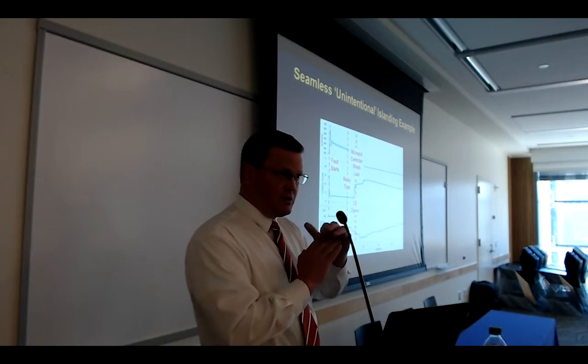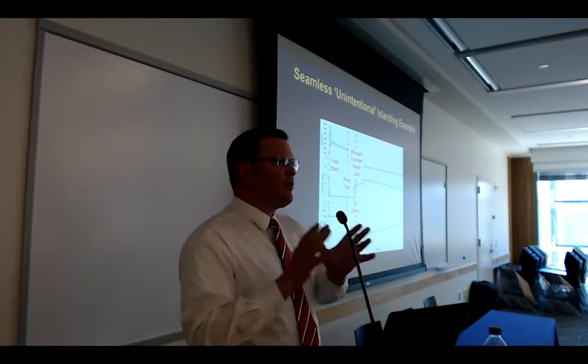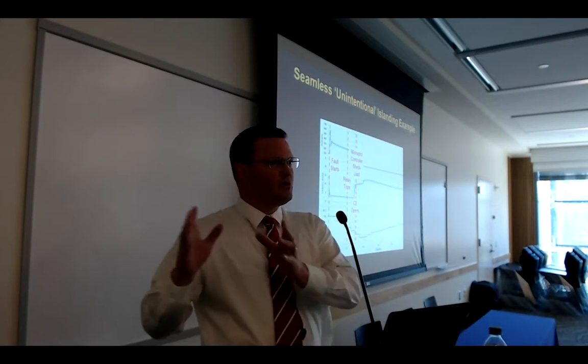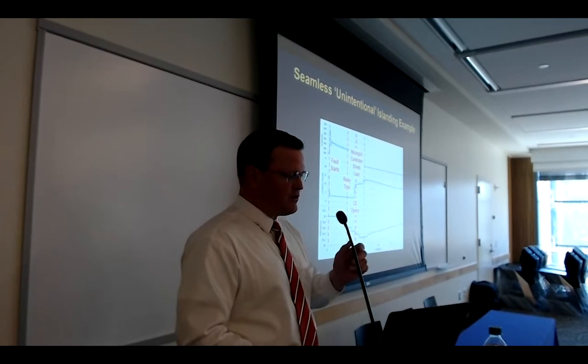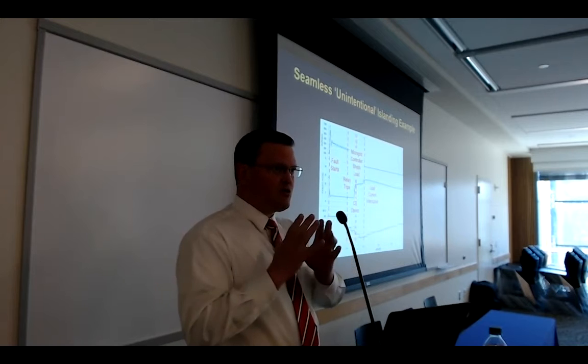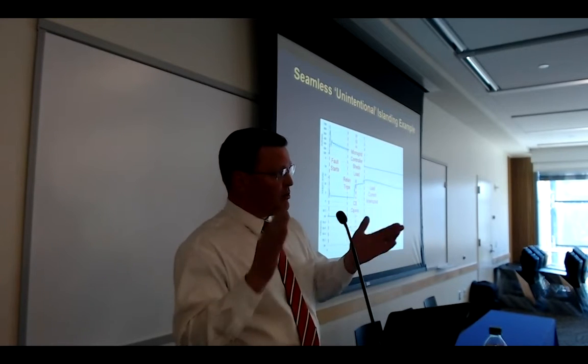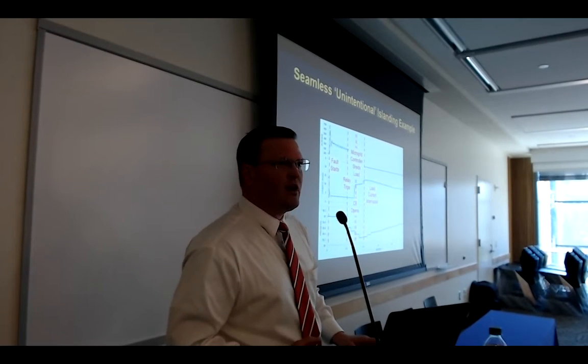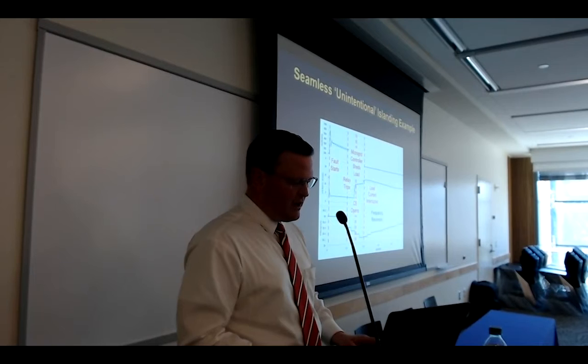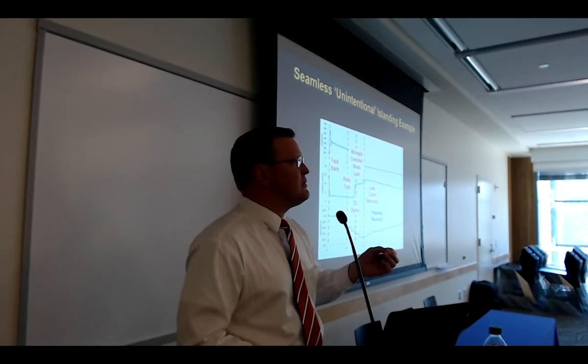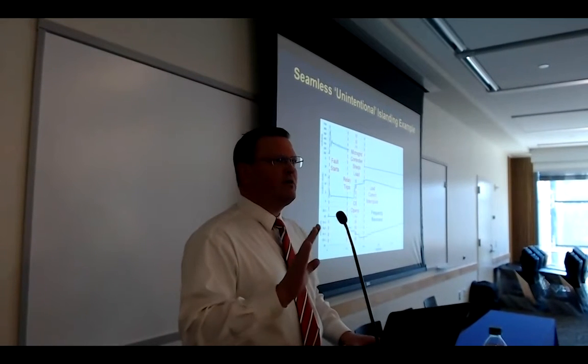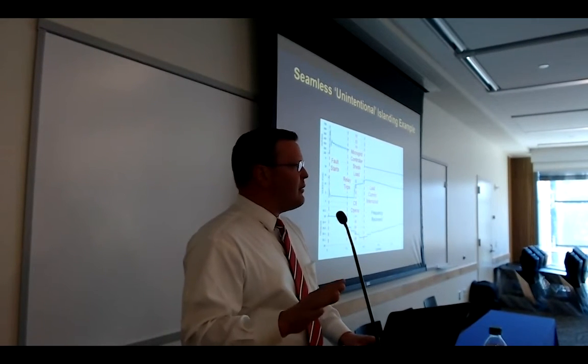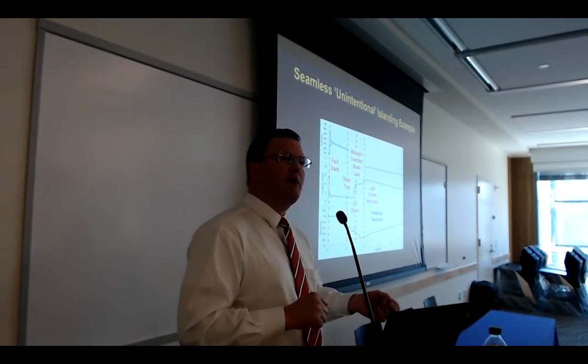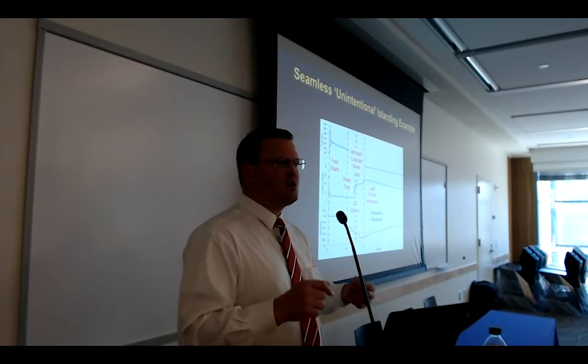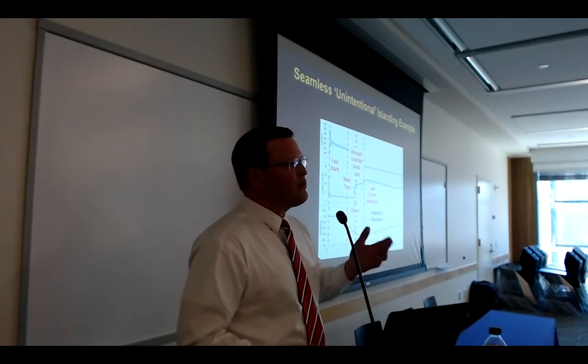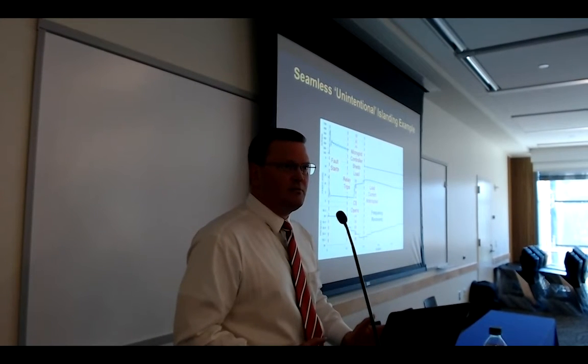The microgrid controller, within 16 milliseconds, said, okay, you don't have enough generation to support your load, so I'm going to go shed some electrical load. So it shed the load. It made a decision so quickly that, again, we wait for the breaker opening time. That transit time between the microgrid controller acting and the breaker opening is, depending on the breaker, between 2 and 5 cycles. A cycle and a half is about the fastest you can buy today. And voila, you have an unintentional yet seamless islanding event. This is day in, day out the job of a protective relay when configured as point of common coupling protection and control. Most microgrid functions are now established as being done in relays.